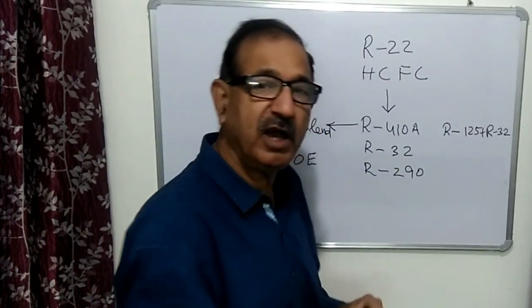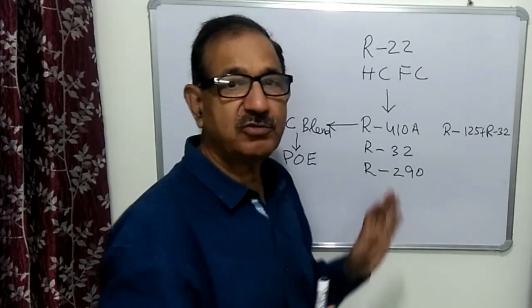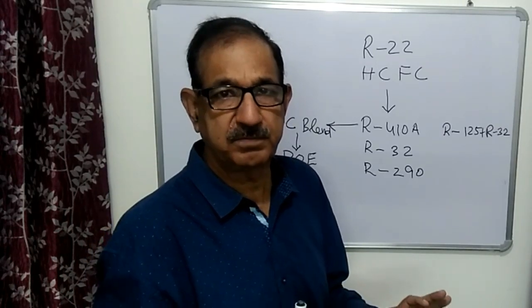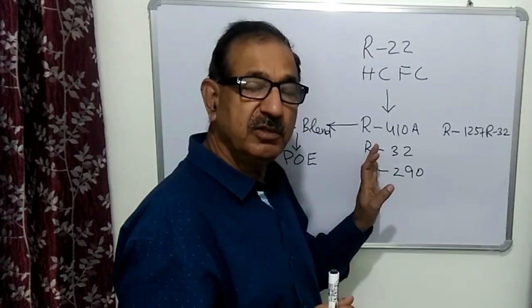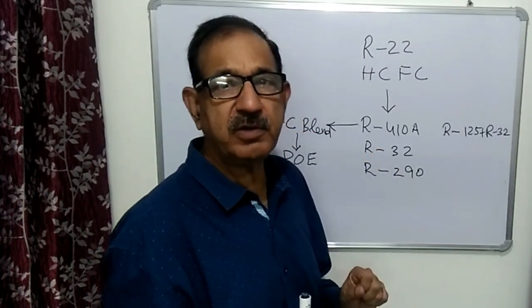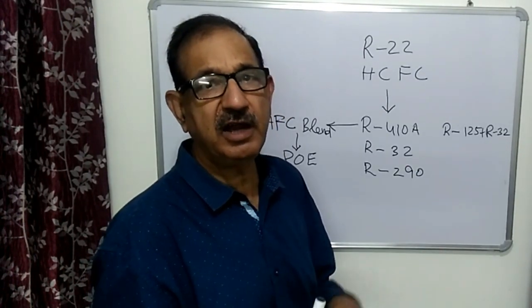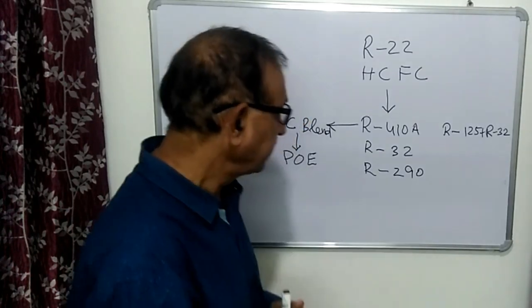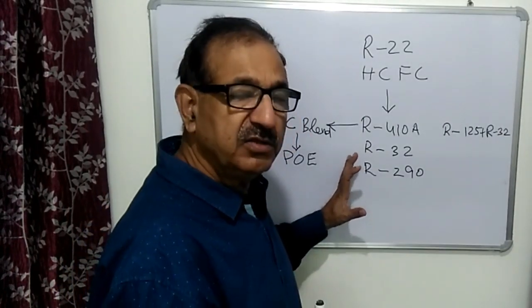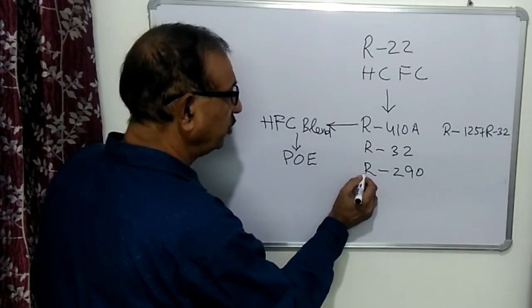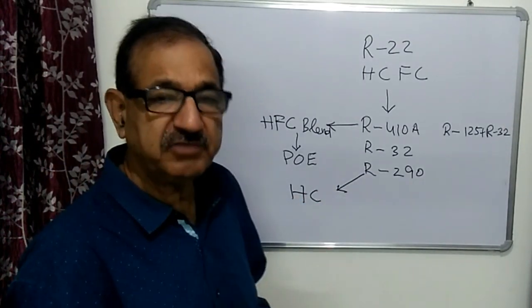For R32, it is also a very high-pressure refrigerant like R410A, and it is also a mildly flammable refrigerant, so we have to take care of flammability issues. Similarly, we must use only the recommended gauge manifold, which has a low-side gauge of 500 psig and a high-side gauge of 800 psig.